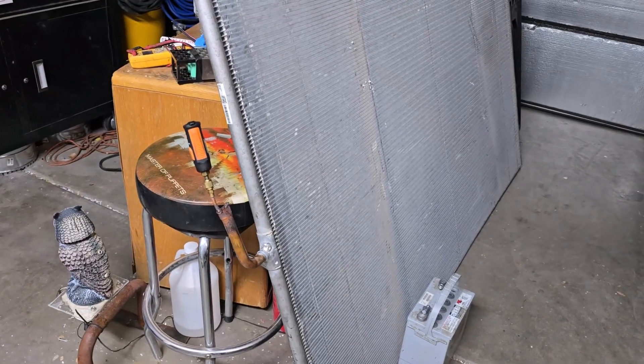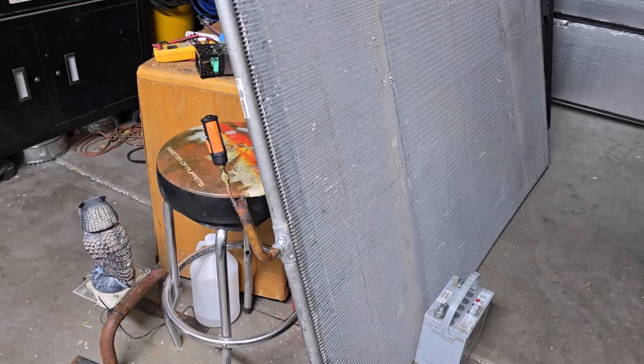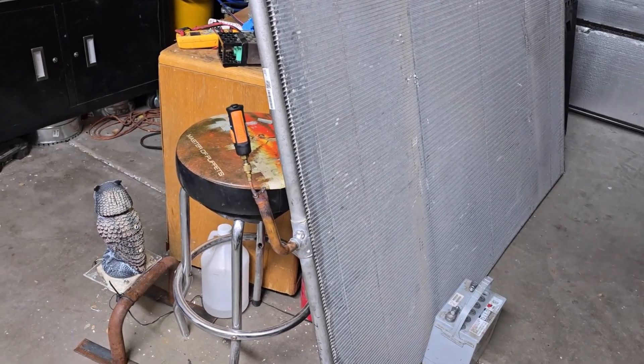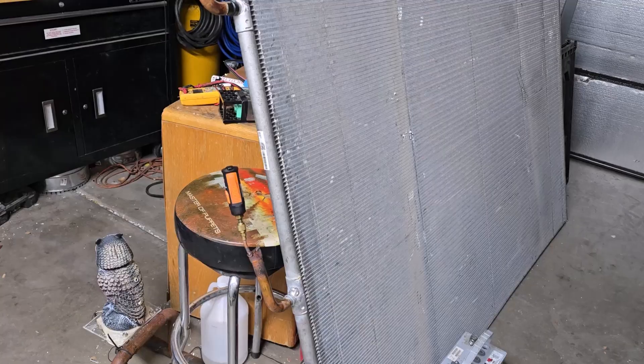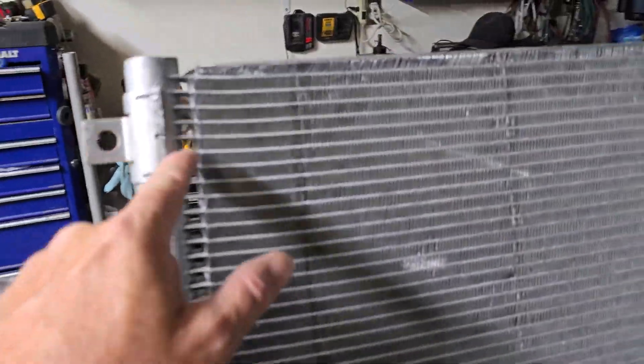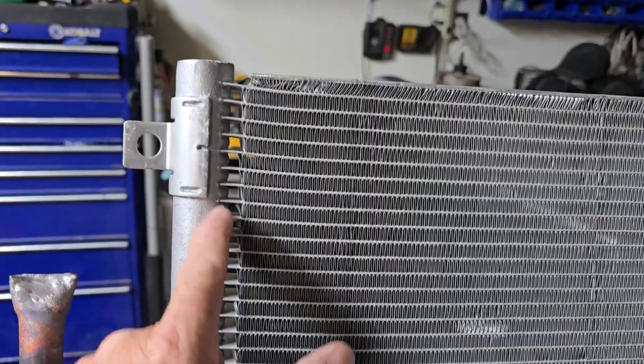I don't want them to risk doing a third coil and maybe getting the warranty rejected. So there's going to be some stuff to tackle in there. If they want to consider this temporary, they could always replace the coil again later. I definitely know now that you can fix these right here. I did not try to take the TIG to anything out in the middle of the coil — maybe someday I'll get a coil that leaks at one of those joints.